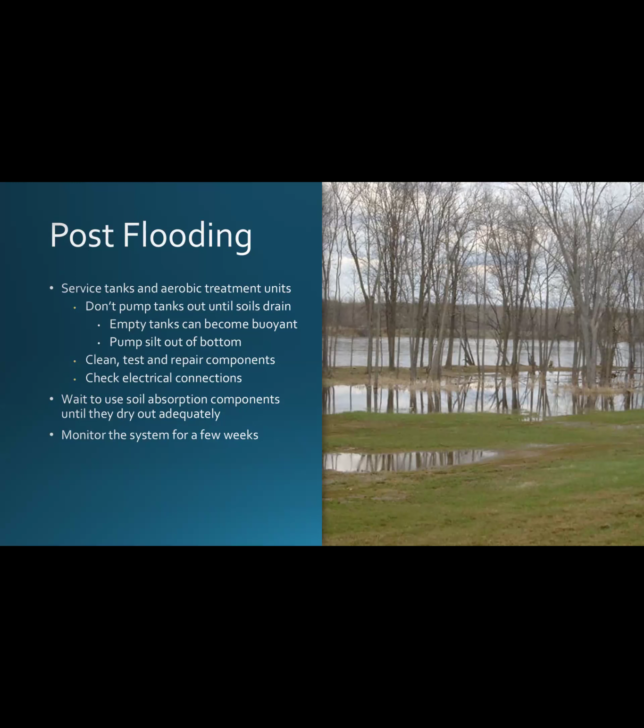Need to pump the silt out of the bottom of them. Sometimes there is infiltration, or we'll pull the risers apart, or we may have some surface infiltration to the top if things didn't work out, especially on sites that may not be in a floodplain and we just had some flooding anyway. You need to pump the silt out of them. And then, as part of the inspection, we need to clean, test, and repair any components, look for any damage, make sure everything's good.